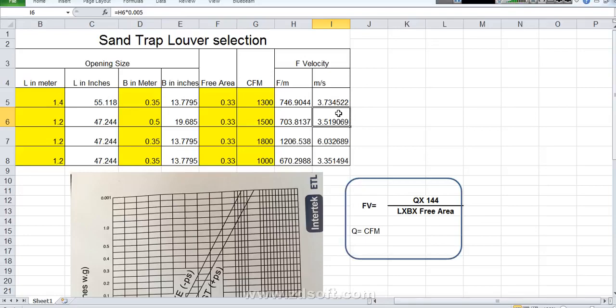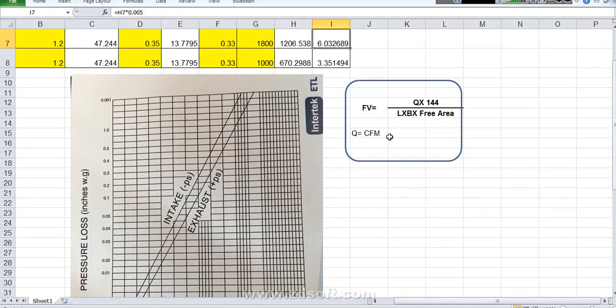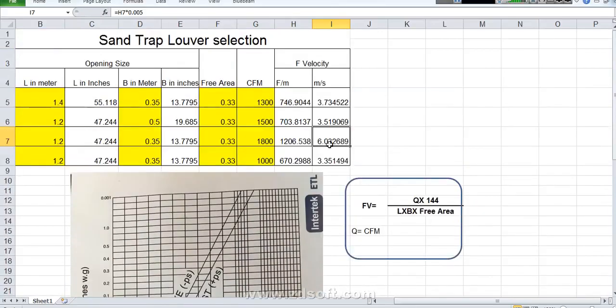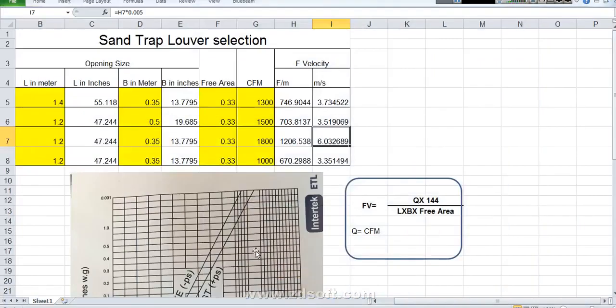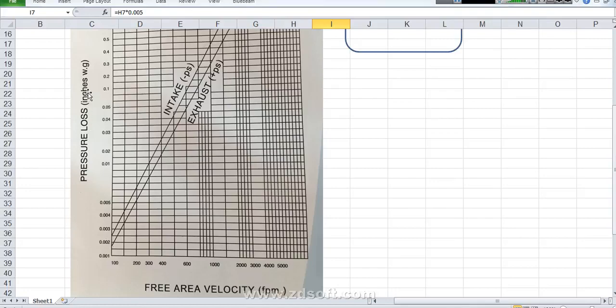3.5 meter per second. This is the comfortable area. In this speed the air is passing outside. It will be safe and the sound will be very less. If it is 5 or 6 there is noise in the sand trap louver. Like this you can change the selection, the sizing. You need to work on it. Then you can change the sizing. What else I told you. Sand trap louver sizing, sand trap louver friction loss. Friction loss we already find it.